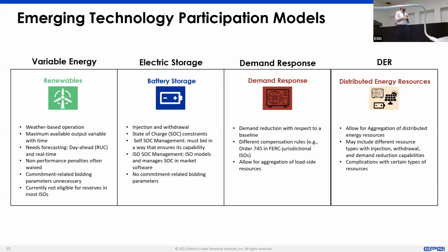Battery storage is obviously a very unique technology. It can inject energy and it can withdraw energy. It has an energy limitation through its state of charge, and different ways of how that state of charge can be managed, whether it's from the ISO, including that in its software, or if it's through the asset in its offer strategy. And again, no commitment parameters for that storage facility, but you have these state of charge parameters that might require additional telemetry, for example.